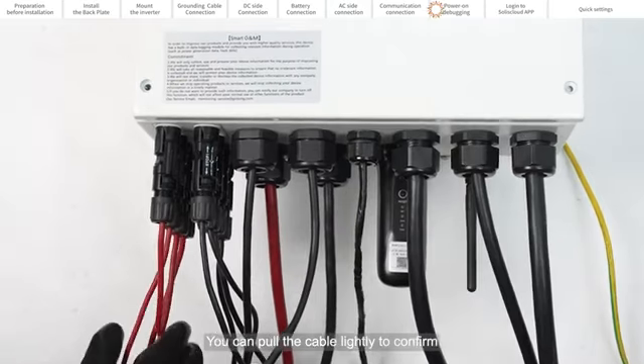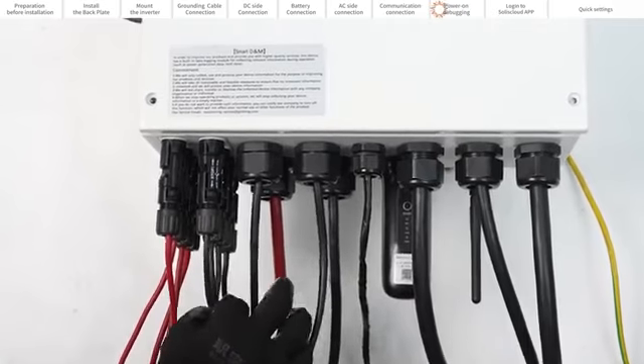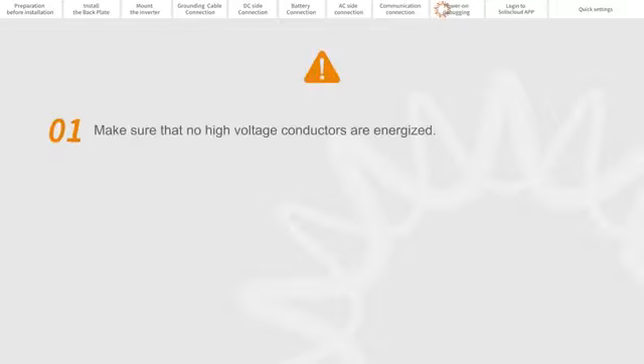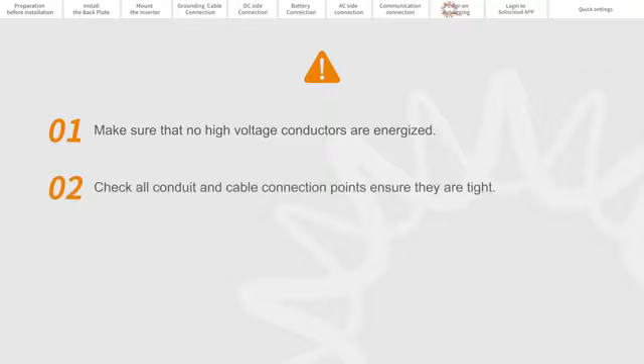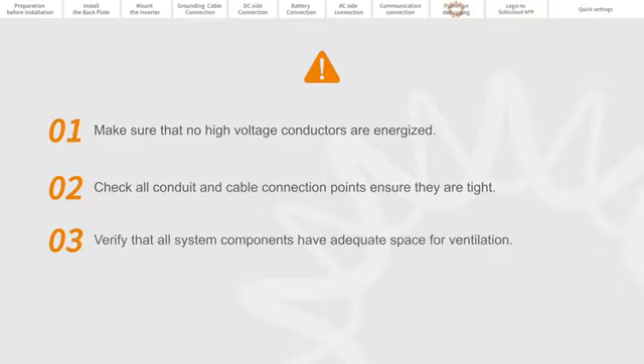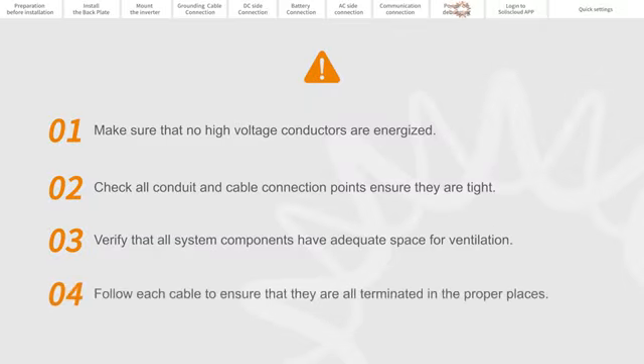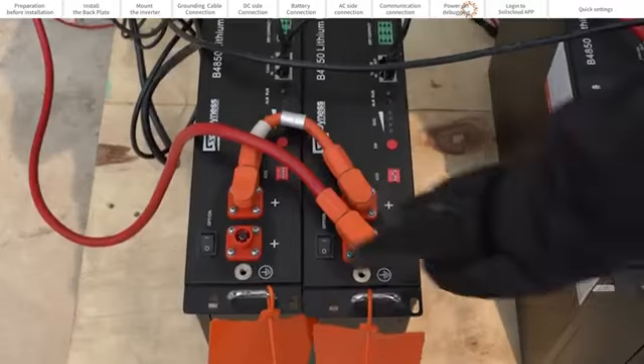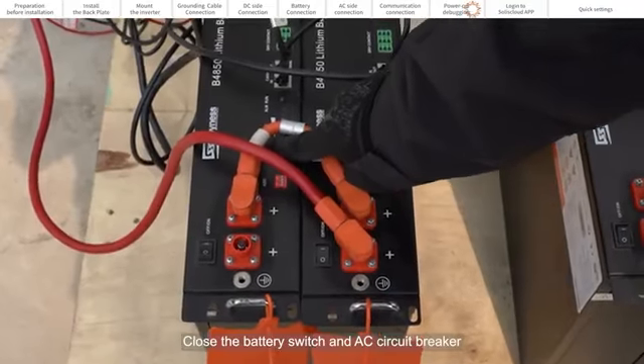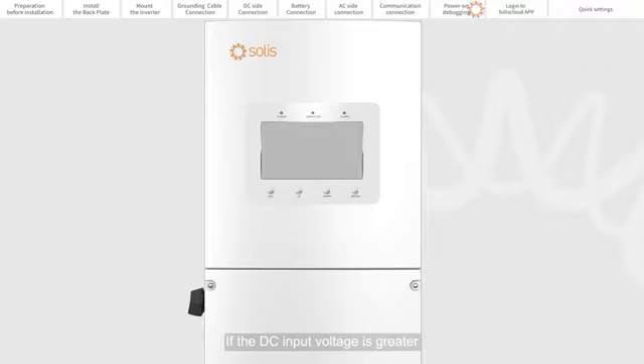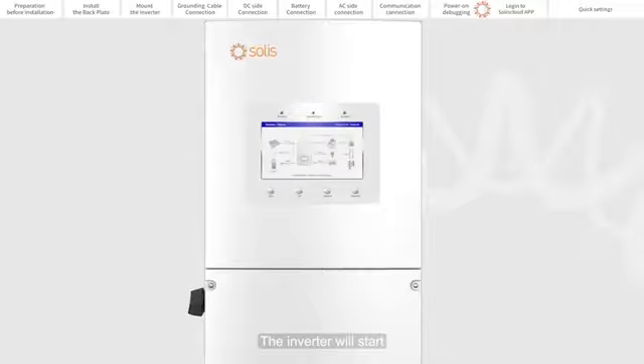You can pull the cables lightly to confirm. Ensure that no high voltage conductors are energized. Check all conduit and cable connection points and ensure they are tight. Verify that all system components have adequate space for ventilation. Follow each cable to ensure that they are all terminated in the proper places. Close the battery switch and the AC circuit breaker. Close the DC switch. If the DC input voltage is greater than the startup voltage, the inverter will start.